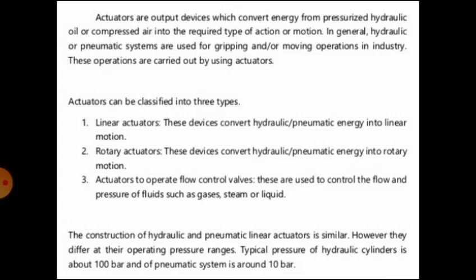Second are rotary actuators — these devices convert hydraulic or pneumatic energy into rotary motion. Third are actuators to operate flow control valves, which are used to control the flow and pressure of fluids such as gases, steam, or liquid. The construction of hydraulic and pneumatic linear actuators is similar; however, they differ in operating pressure ranges. A typical hydraulic cylinder operates at about 100 bar, while a pneumatic system operates at around 10 bar.